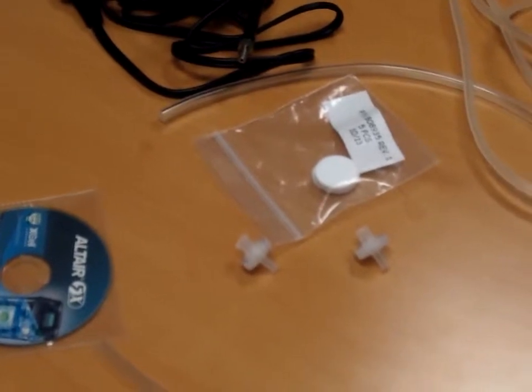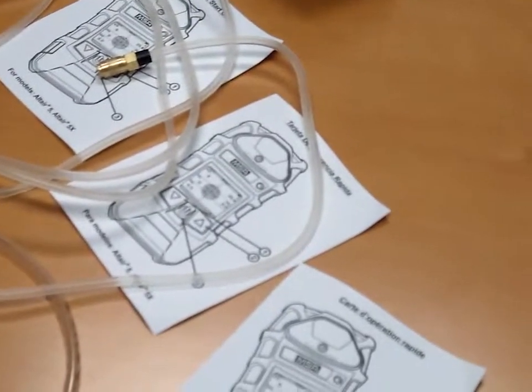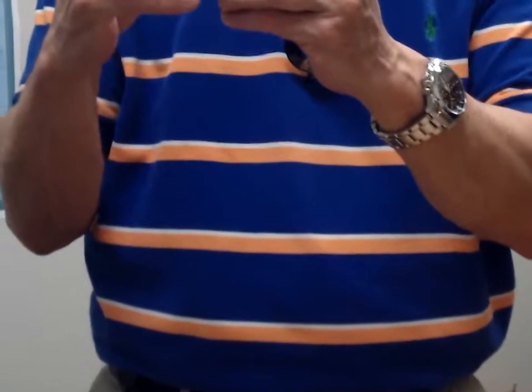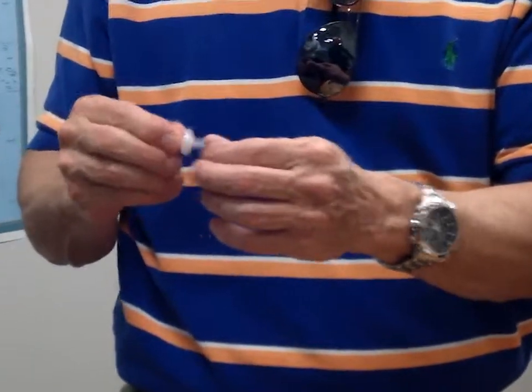It's shot, yeah. If you're using it and your pump goes into alarm, the first thing you want to check is the filter on there. If it is filled up with water, typically they've expanded to the point where it won't pass air. Little tip I've learned working in a humid tropical environment is that if there's a lot of humidity, moisture in the area, you could expand one of these filters out to the point where it'll close off and you never sucked up any water. It's just the humidity in the air. Yeah, so you may want to include that when you do that.